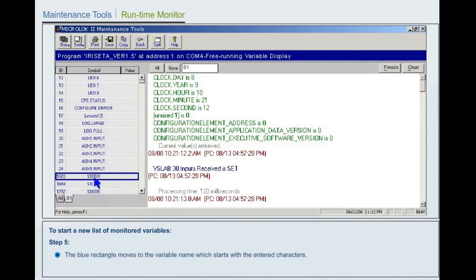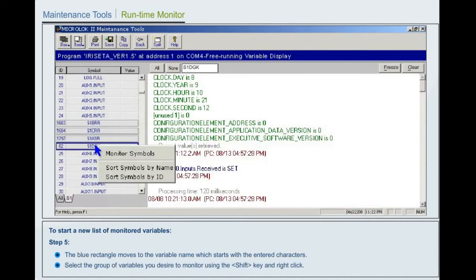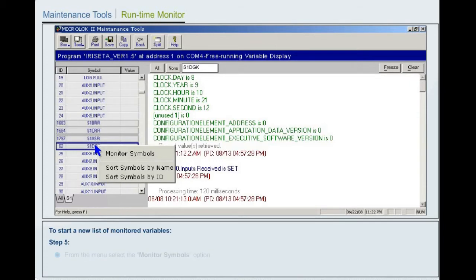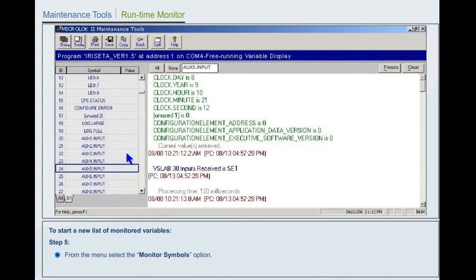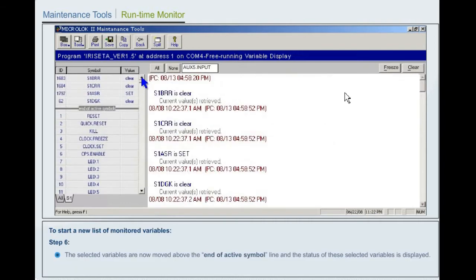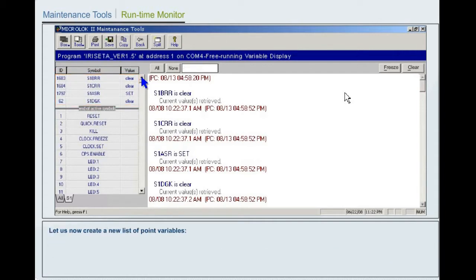Step 5. The blue rectangle moves to the variable name which starts with the entered characters. Select the group of variables you desire to monitor using the Shift key and right-click. From the menu, select the Monitor Symbols option. Step 6. The selected variables are now moved above the end of active symbol line and the status of these selected variables is displayed. Let us now create a new list of point variables.